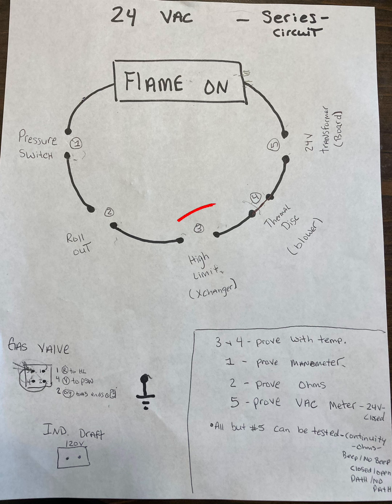Number 3 is my high limit switch. This is a temperature sensitive switch, and it is found right inside of the heat exchanger. The whole purpose of this job is a safety feature. All of these are safeties. If something is stuck in the side of the heat exchanger, say the homeowner wasn't running a filter and a piece of paper got shoved up in there and it's about to catch on fire, or a cat or an animal or something's going on in that heat exchanger. Or let's say we have a failed heat exchanger situation, rusted holes all through it. There's a lot of things that could be going on in the heat exchanger.